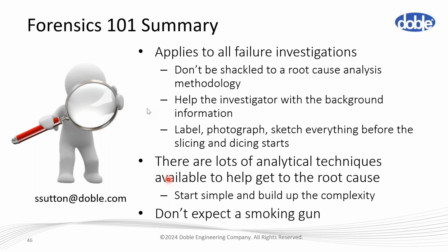How can the cable be prevented from failing? Well, that's hard, because in some instances, I had a case a few years ago where we thought that there was a design issue with the cable and it was going to fail in quite an unusual manner. And we proposed putting some permanent monitoring in to test the hypothesis as to how it was failing. Again, we made the recommendation earlier this year. I had an email from that company saying, we found your name on a report from 5 years ago. We've just had another failure.